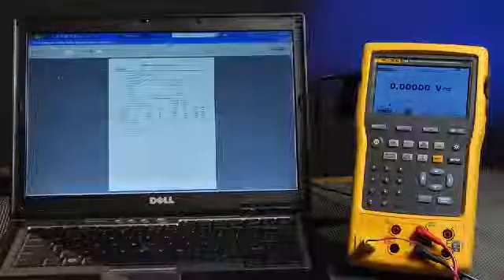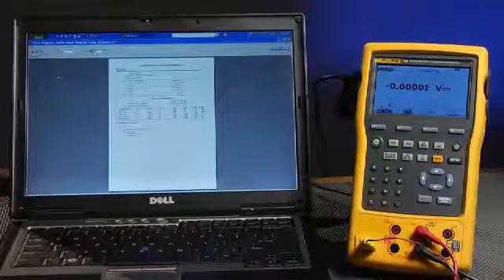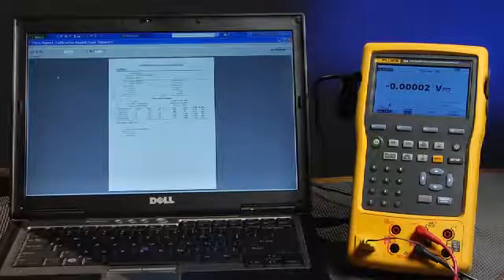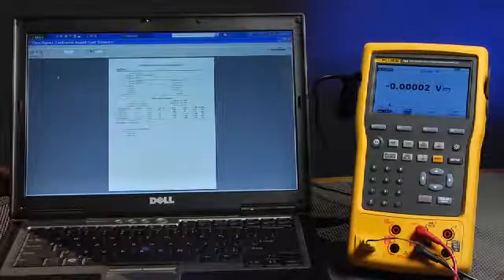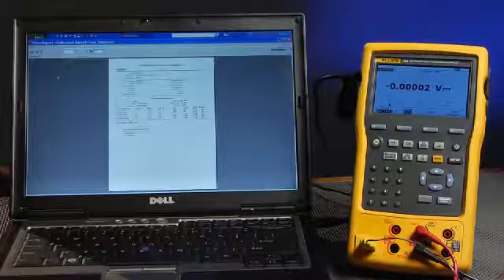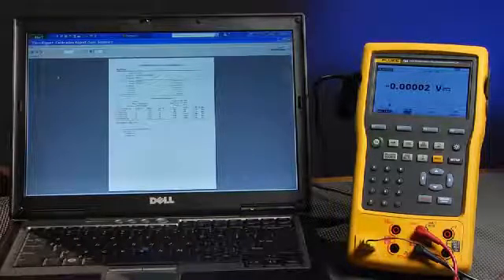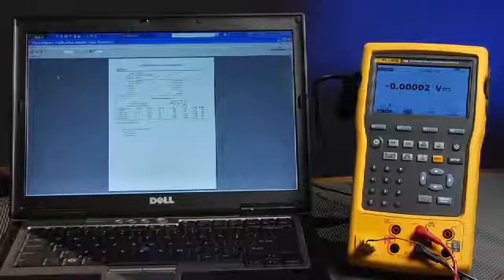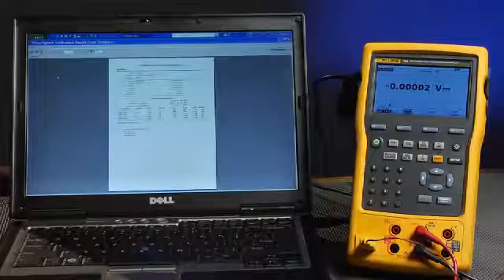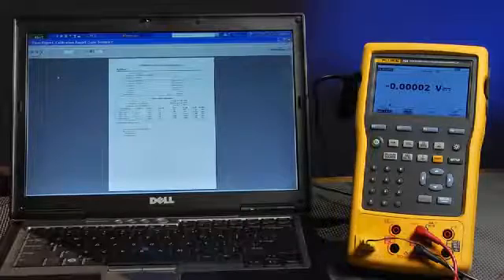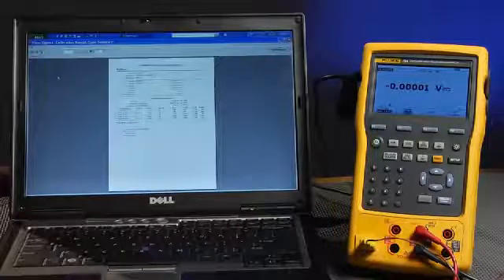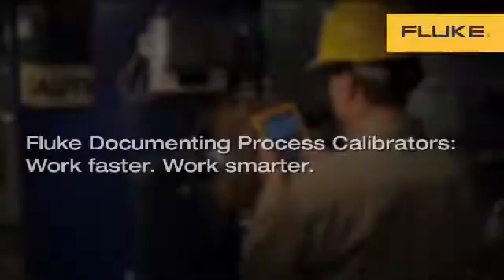We've gone full circle. We've created a tag in DPC Track 2 software, loaded into the Fluke 754 documenting process calibrator, documented the results of the transmitter using a tag that was downloaded. Uploaded the results back to DPC Track 2 software, reviewed the results, and printed the report.